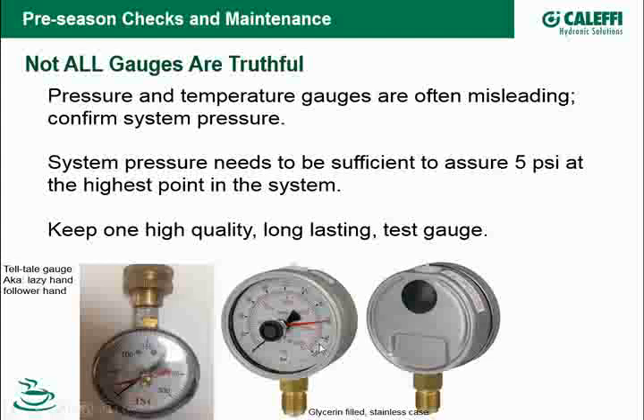But for boiler work, for hydronic work, I would get a gauge like this with a 30-pound gauge, so it's accurate. The resolution's a little bit better than the pressure gauge that goes up. Certainly you don't need a 200-pound gauge on your boiler work, but get a 30-pound glycerin-filled gauge with this little follower hand, and that should last you for years. It'll be accurate. And you can put a connection like this on, because what you could do with that gauge is then most boilers have a drain cock on them somewhere. You've got some sort of hose connection. You can screw it right onto that hose connection and open up and see what the pressure is and compare it to the gauge that might be on the system. So that's a little tip for you.